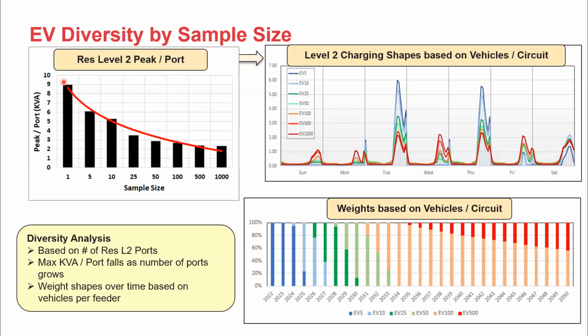But as we add in more ports, we see the peak per port decline, since we're adding in diversity. So for the low voltage network, we need to account for that lack of diversity. This is particularly an issue at the transformer level, somewhere between 1 and 5 ports. At the feeder level, it ended up being less of an issue; diversity actually increased a bit quicker than I expected.